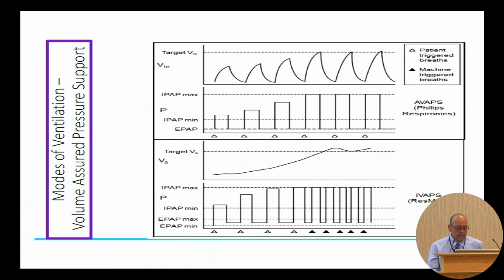This is the one from ResMed, which has a different target; they go by the alveolar volume, but it pretty much functions the same way. So you have an auto EPAP to keep the airway open, and then you have an IPAP minimum and an IPAP maximum, and it's doing the same. Whenever the alveolar volume is below the target, the IPAP pressure is going to increase automatically. Here you see these black arrows. That's the backup rate.